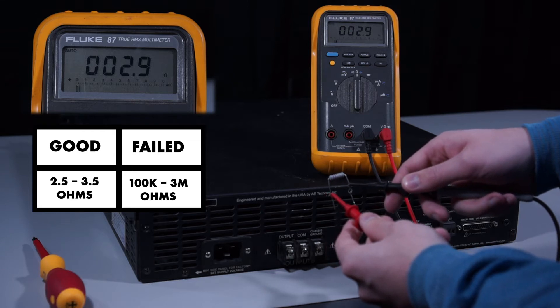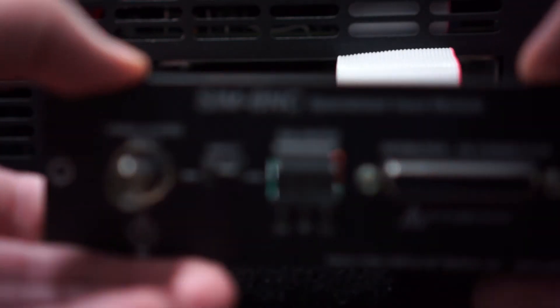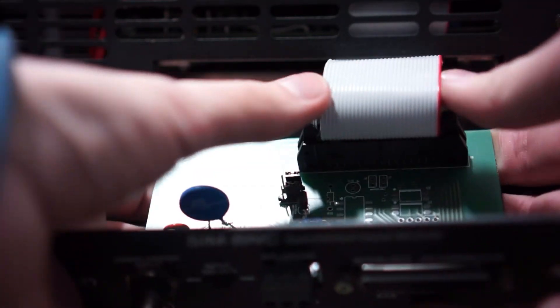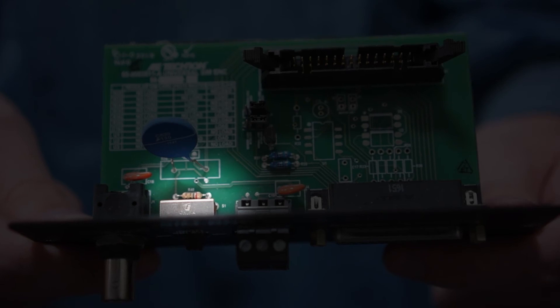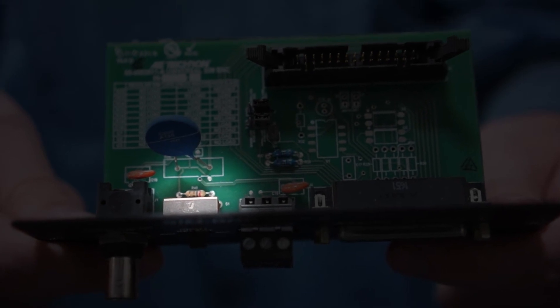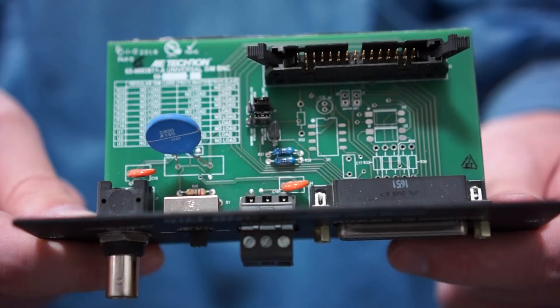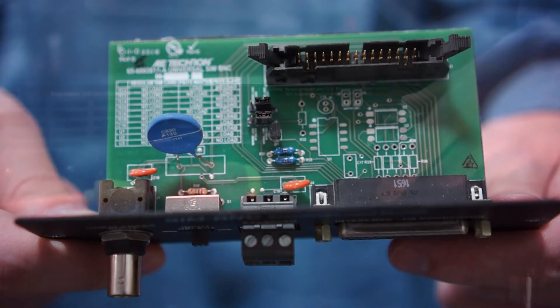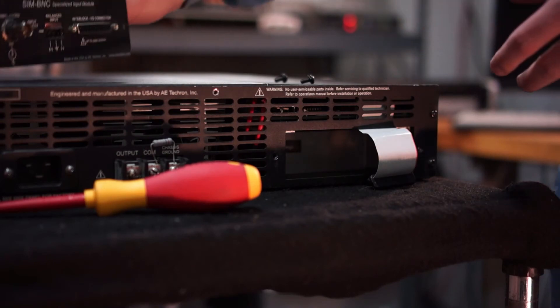The second fuse is another 2.7 ohm resistor, and it is located in the specialized input module or SIM card. This resistor protects the amplifier when potentially damaging voltages or currents are presented to the amplifier's input.